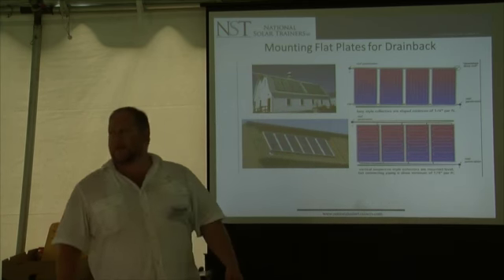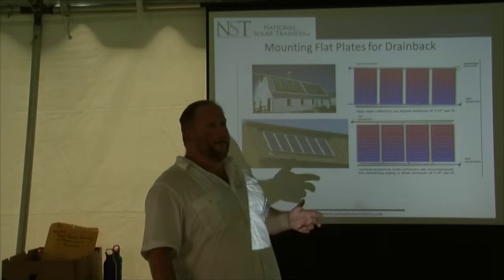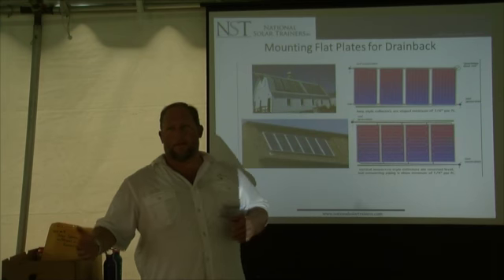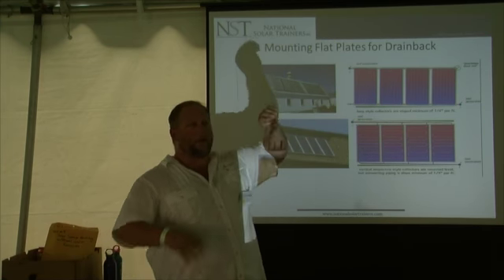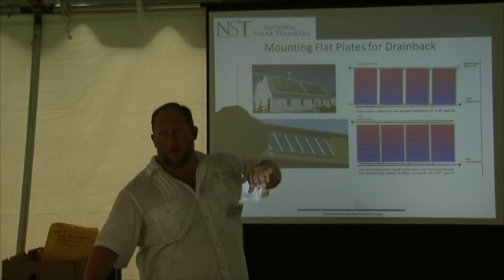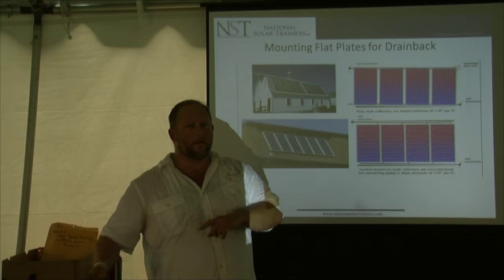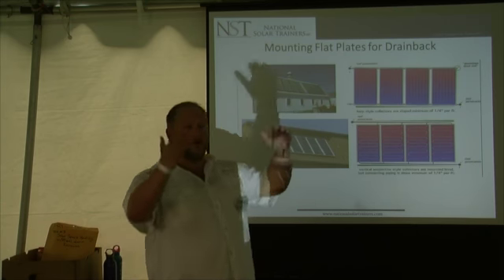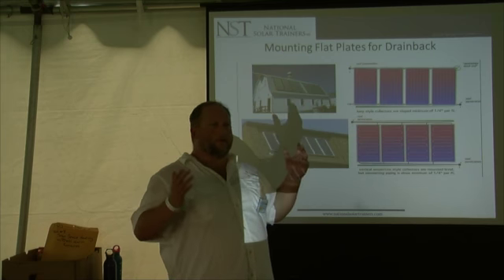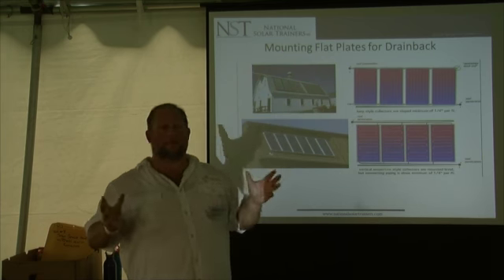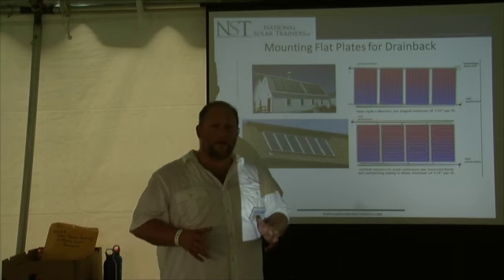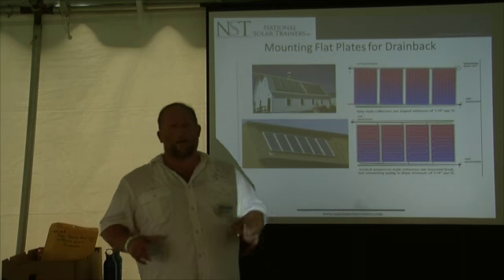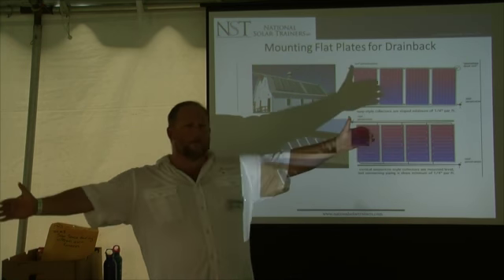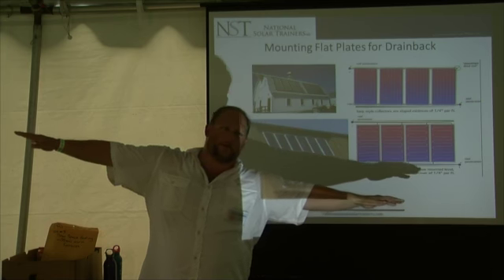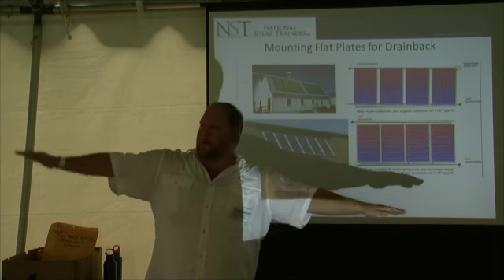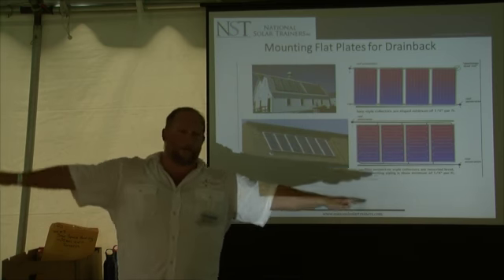And drainbacks are more efficient because drainbacks allows you to remove a heat exchanger. Right? So I could pump to my collectors right down directly into my floor and then back up to my collectors because I'm pumping water. It's going to drain back at night. All right, which means more efficiency because I was able to remove a heat exchanger if I did a drainback. But I chose not to do a drainback because of aesthetics. Drainback systems have to be tilted 1/4 inch per foot. So if you mount them on your roof at 28 feet, turned out to be a 7-inch drop.